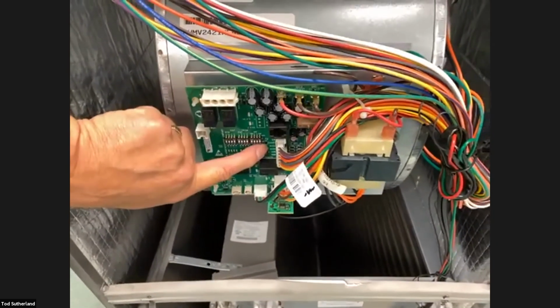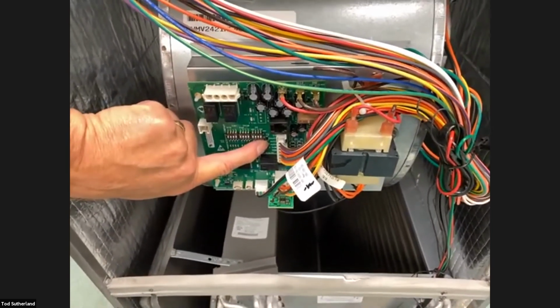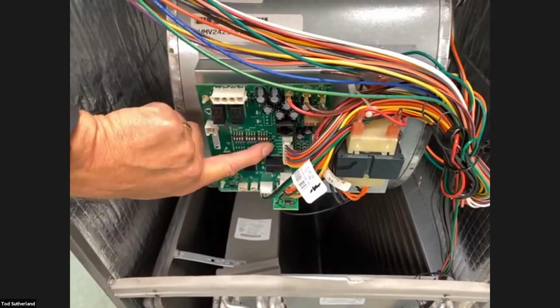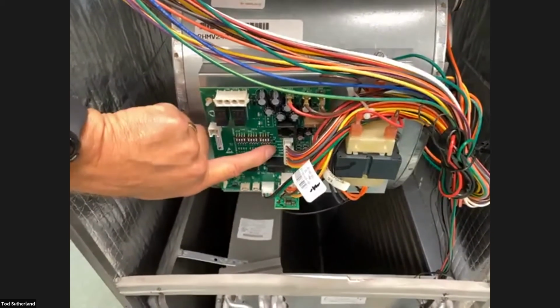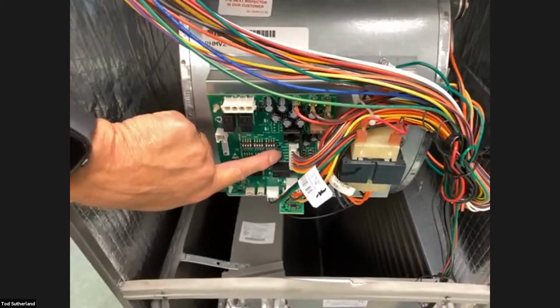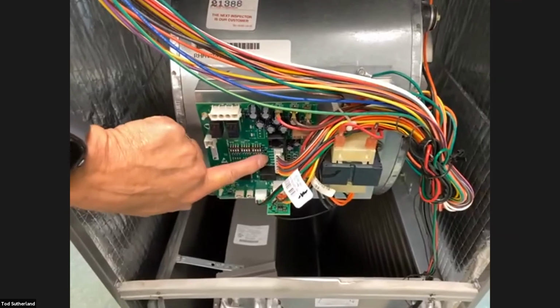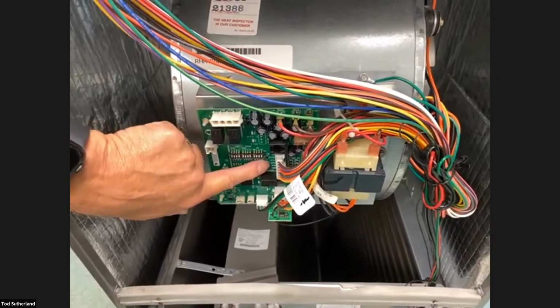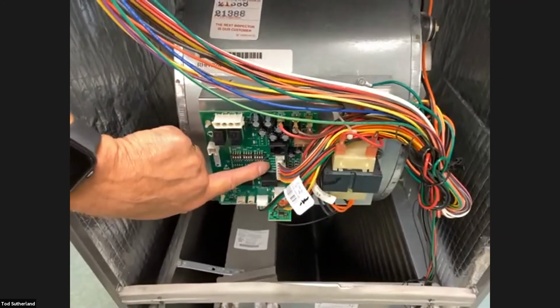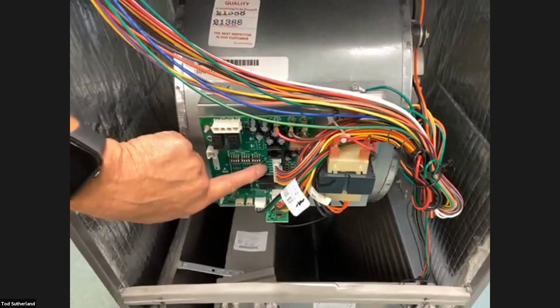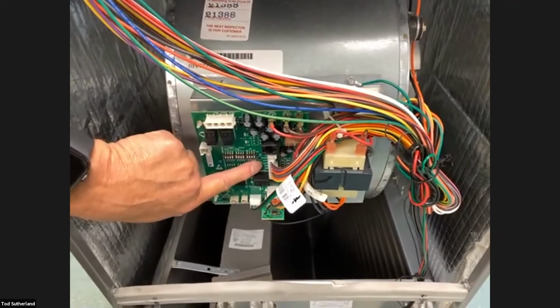Okay, that's your auxiliary common, your auxiliary 1, and your auxiliary 2. Now what you're going to use those for is your float switch. All right, so we do not want you breaking R or common, and most definitely we don't want you breaking E1 or E2, the communication wires.